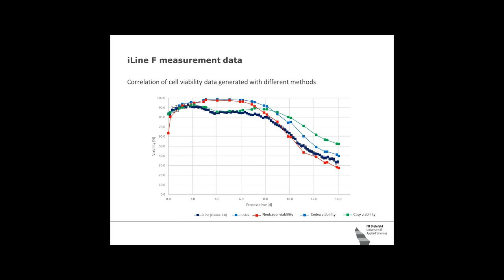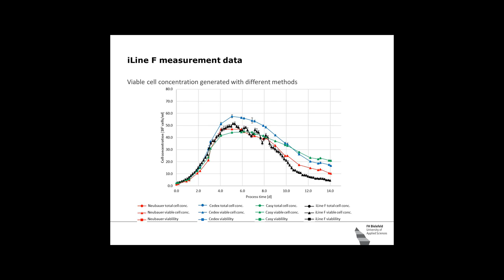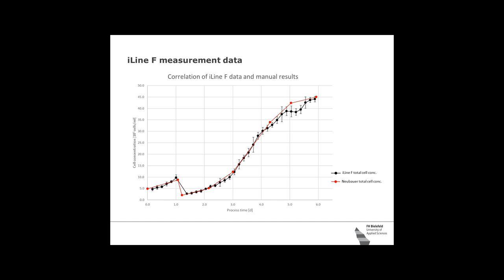I go back again here, that the correlation between the iLine F, the new technology here, and the Cedex is not 100%, but implementing a correlation factor here, you can see that's a different cultivation here. With a growth phase for the first day, and then a dilution step here, and then the culture grows again. So with the correlation factor here, we are able to set the manual cell count and the data generated with the holographic images perfectly together. And that also is true for different batches in different bioreactors at different dates, and with different, you see here in red, BioConnect A, BioConnect B, with different BioConnects.